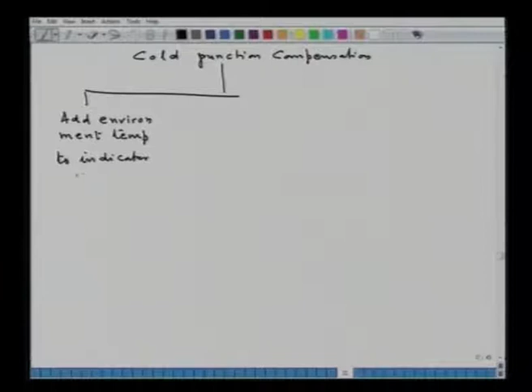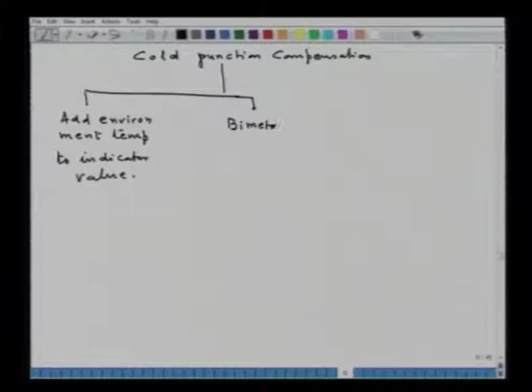Another way, a little bit sophisticated way, is that the indicator needle is connected to a bimetallic spring. That means use of a bimetallic spring, which expands or contracts depending on the changes in the environmental temperature. So, as such you are recording the value after correction of the cold junction temperature, because you now have bimetallic springs and they expand or contract depending on the temperature. This is another way. The third way is the use of thermistors in thermocouple circuits. So, this is how you are going to do the cold junction compensation.